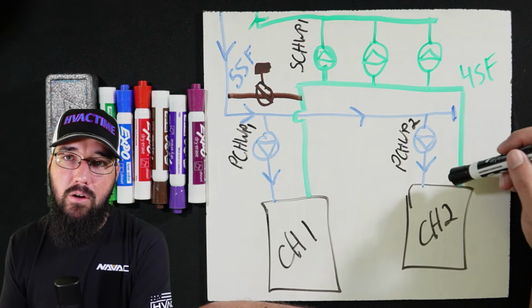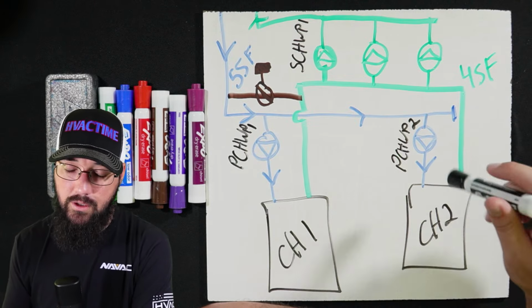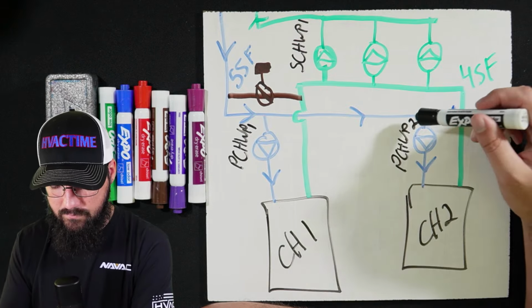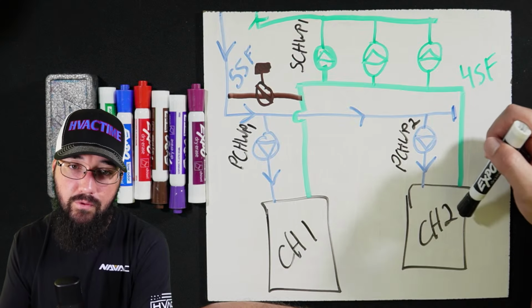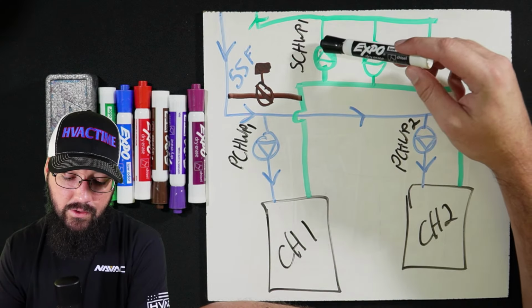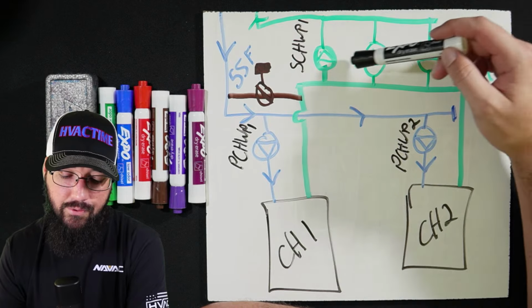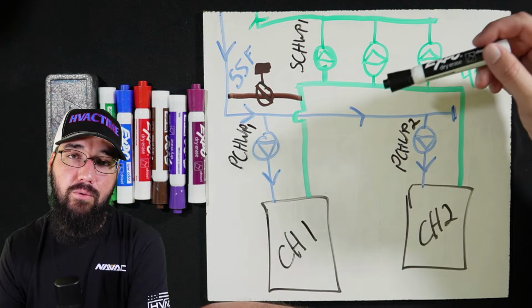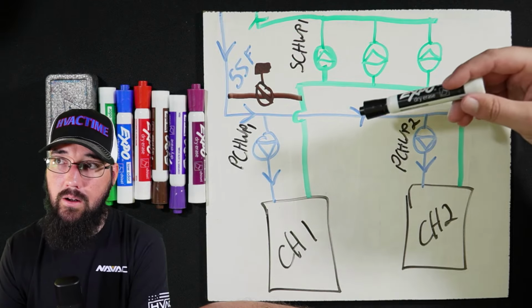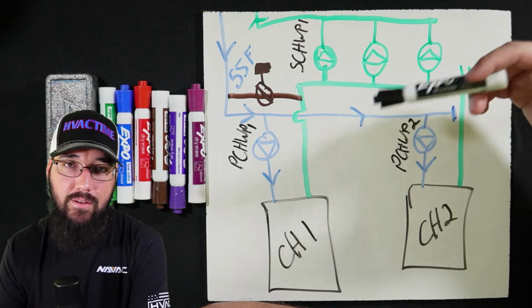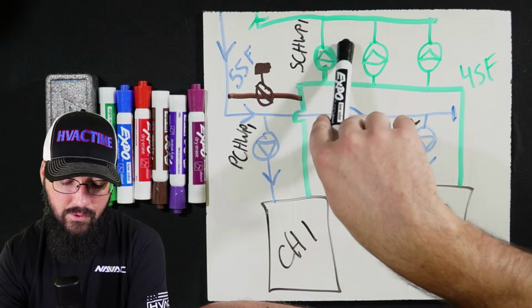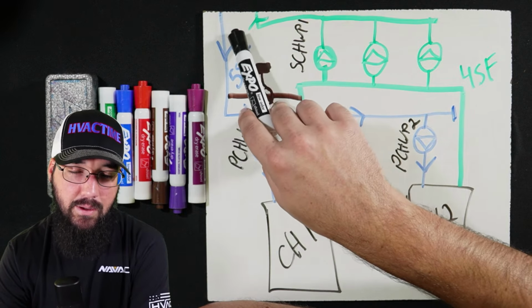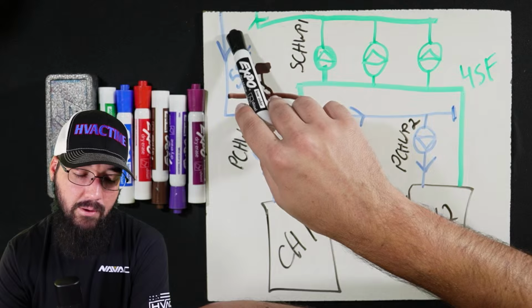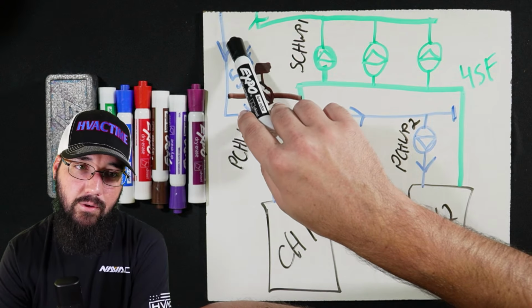So if we only have pump 1 on, or I'm sorry, chiller 1, if we only have chiller 2 on, and we have our primary chill water pump 2 serving that chiller, we could still have a full load and need all three of these secondary pumps to maintain flow through the loop and to get water to all of the load devices, whether that's air handlers, whatever the case. And we're going to monitor this based off of a DP across our loop. So we're going to be measuring differential pressure between the supply and return water, or the plant leaving water and the plant entering water, right? We're going to be monitoring a DP here.